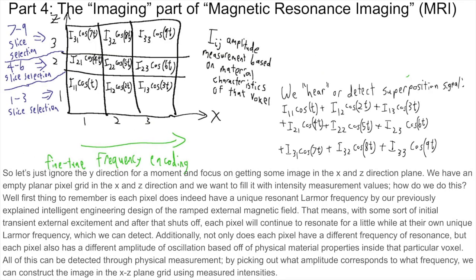So let's just ignore the Y direction for a moment and focus on getting some image in the X and Z direction plane. We have an empty planar pixel grid in the X and Z direction, and we want to fill it with intensity measurement values. Each pixel does indeed have a unique resonant Larmor frequency by our previously explained intelligent engineering design of the ramped external magnetic field. That means with some sort of initial transient external excitation, and after that shuts off, each pixel will continue to resonate for a little while at their own unique Larmor frequency, which we can detect. Additionally, not only does each pixel have a different frequency of resonance, but each pixel also has a different amplitude of oscillation based off of physical material properties inside that particular voxel. By picking out what amplitude corresponds to what frequency, we can construct the image in the X-Z plane grid using measured intensities.